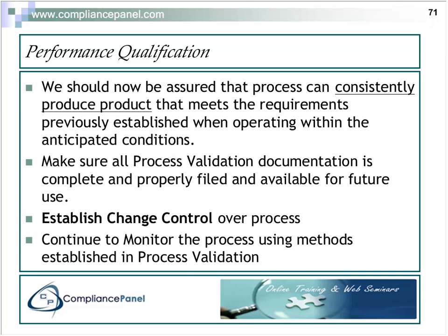We need to establish change control again. We talked about that at the end of OQ. We need to make sure that from this point forward, change control is locked in and no changes can be made in the process without going through that. Continue to monitor using the methods established in process validation. In other words, are we going to use, for instance, SPC, or some other tool to monitor the process? Perhaps we have automated inspection equipment, something like that.